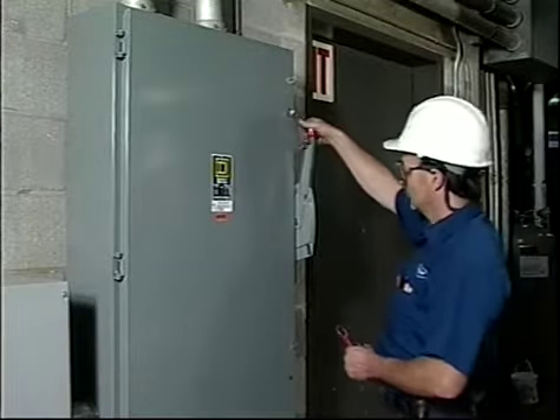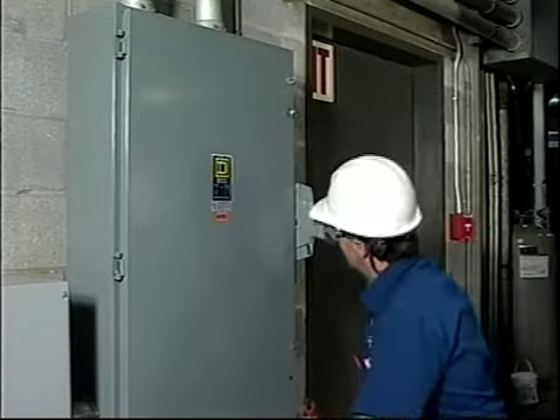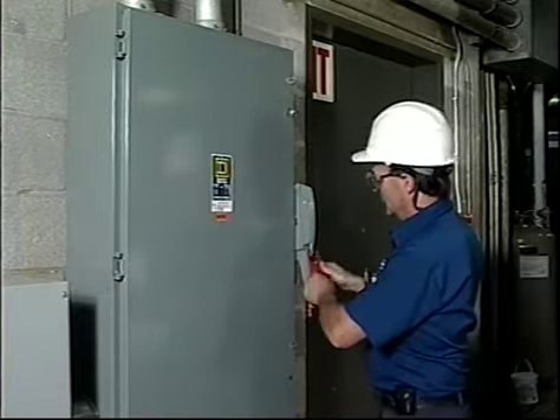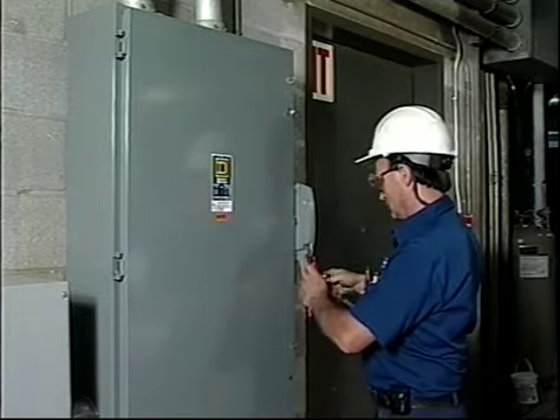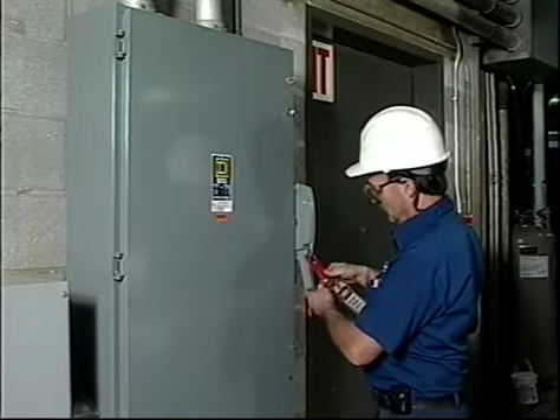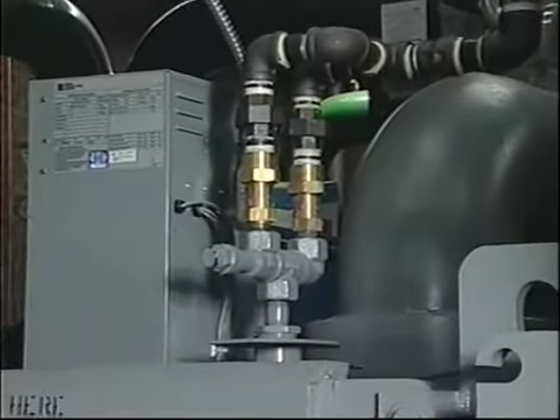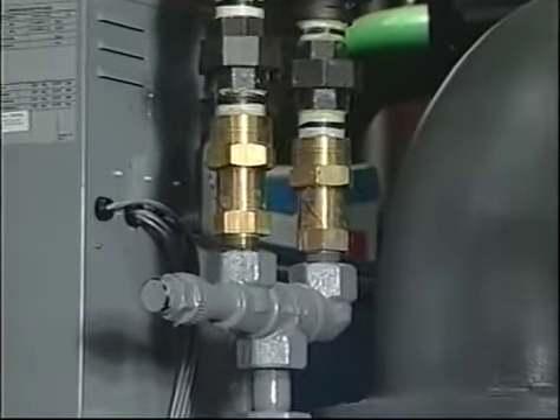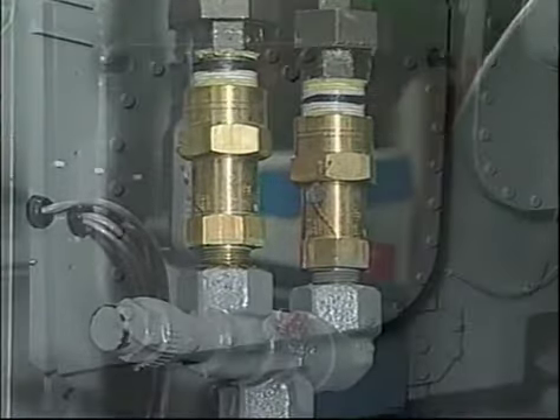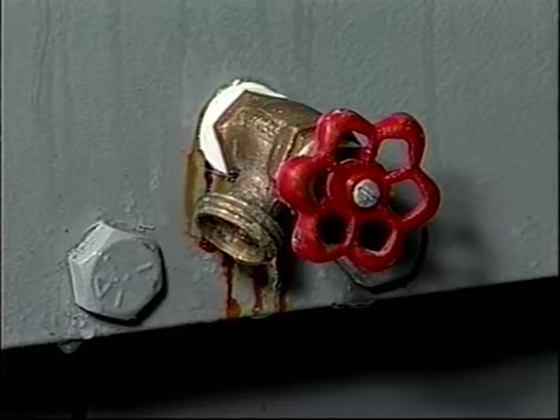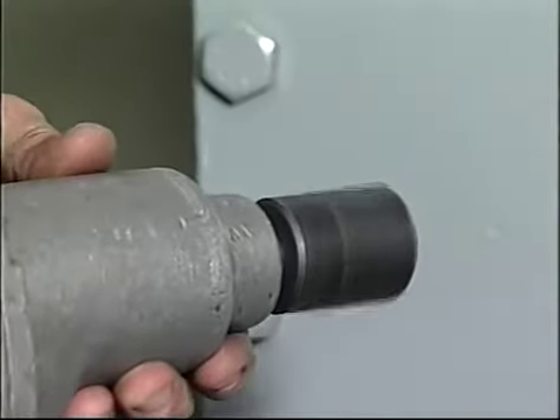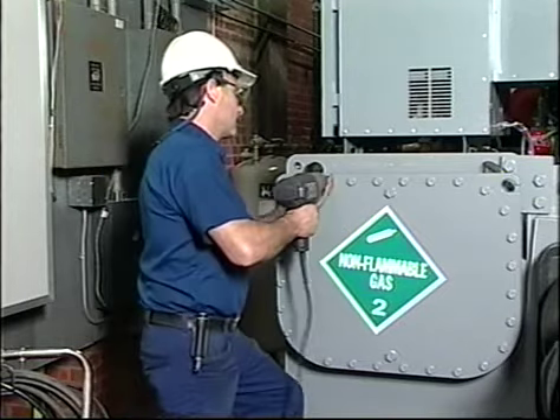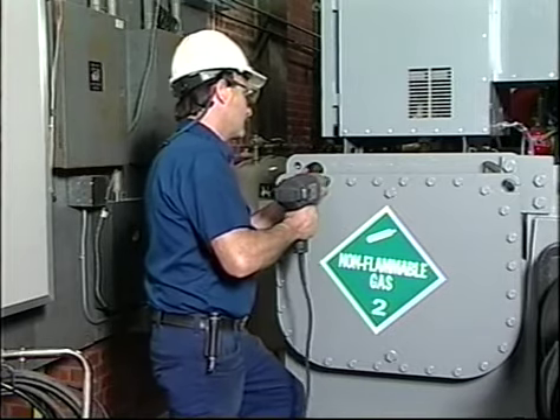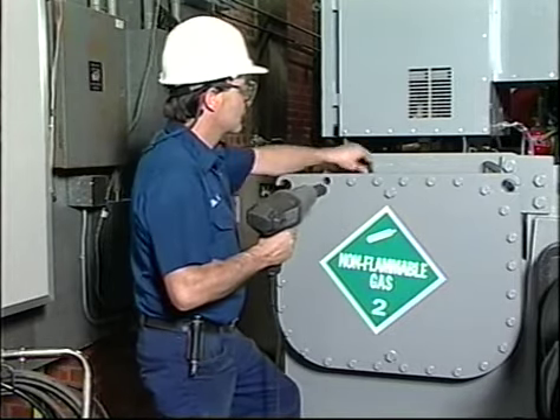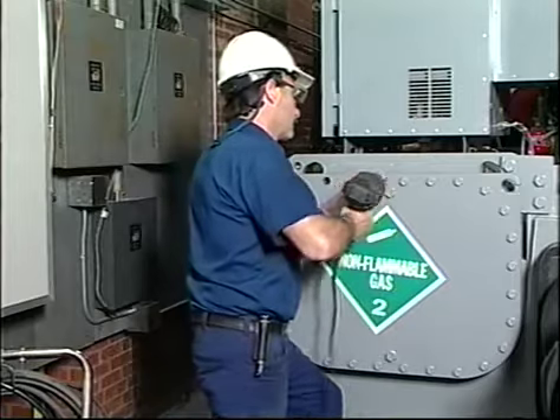When working on electronics, shut off the starters as well as the machine because automatic mechanisms may activate the part you are working on. When replacing any part, be sure to use only material that meets code requirements. Don't vent or empty water boxes unless you are absolutely sure of what you're doing. Don't unscrew water box cover bolts unless you are sure the water box is completely drained. Don't loosen any packing gland nuts unless you are sure the threads are engaged.